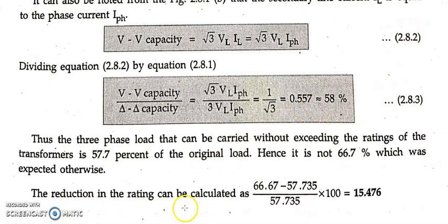So the reduction in the rating can be calculated as follows. I told you in layman's language we understood that it is around 66.67, but as a matter of fact it is around 57.7%. So the total reduction in terms of actual reduction is how much? 15.476. Just subtract 66.67 minus 50. Actually it should be 57.7. Okay, just subtract there, they have made a mistake here, it should be 57.7. So if you take 57.735, then the actual total reduction is 15.476. Okay, just for your remembering sake.